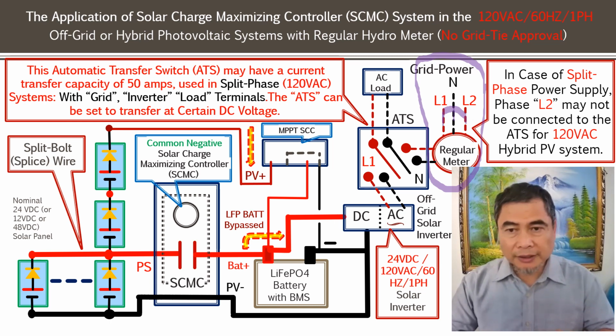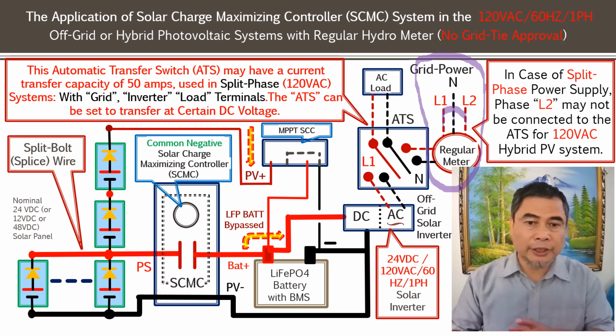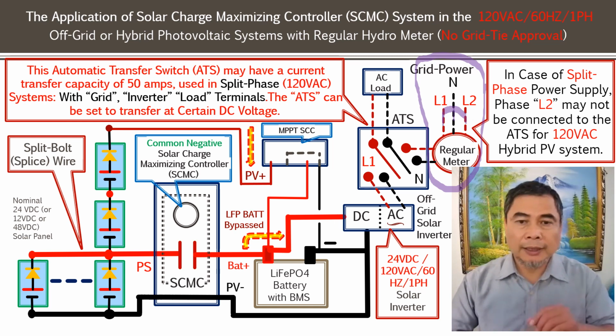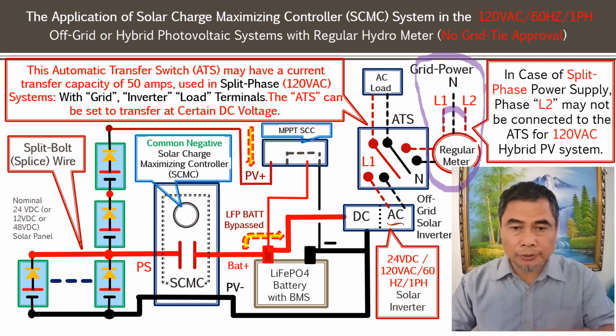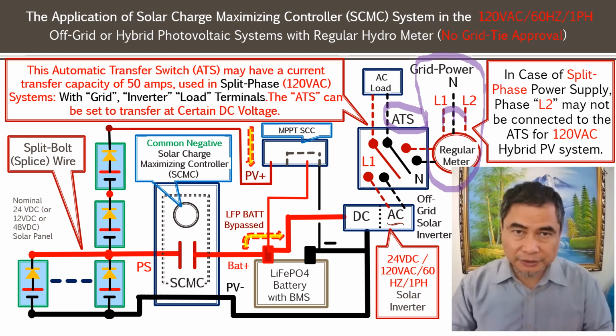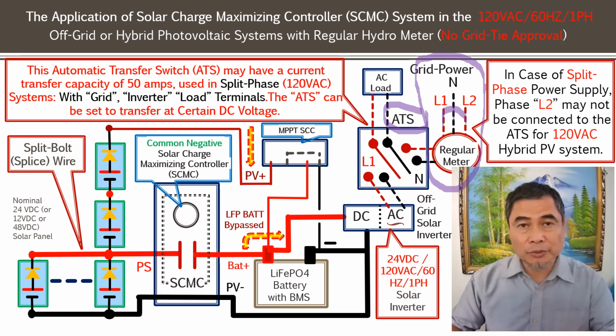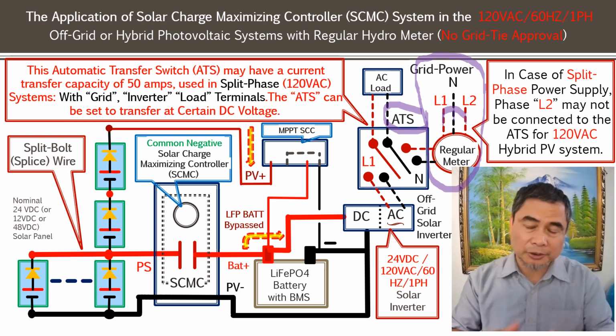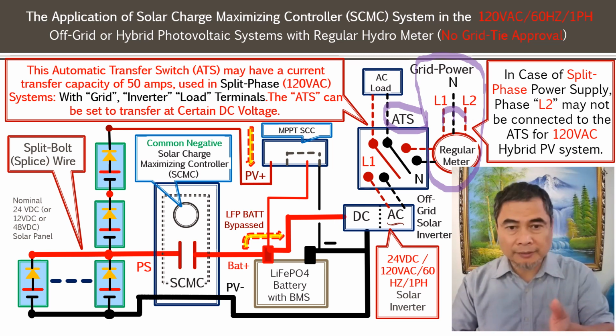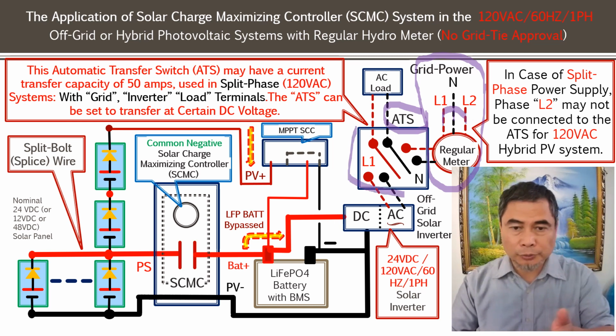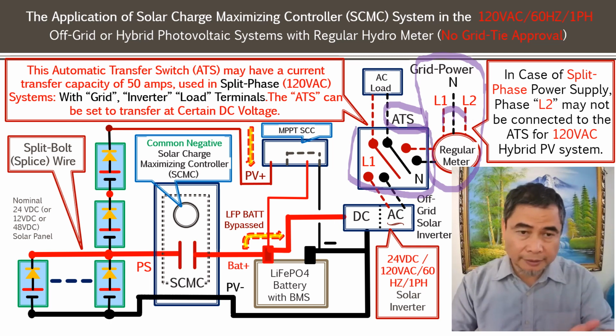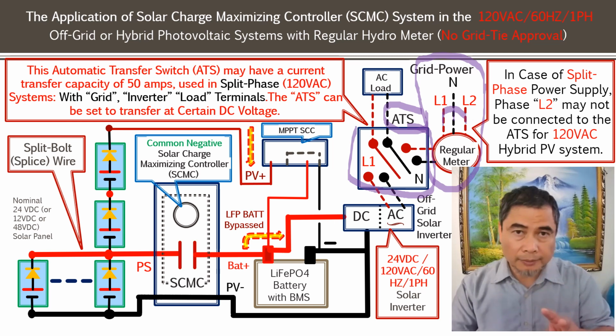For split phase, the inverter design is very difficult and complicated. Also, for the automatic transfer switch, we don't find one available yet that can have 3 lines going in there, L1, L2, and neutral. For this automatic transfer switch design, very convenient with a proper DC setting there, they are currently only available for 2-line connection.